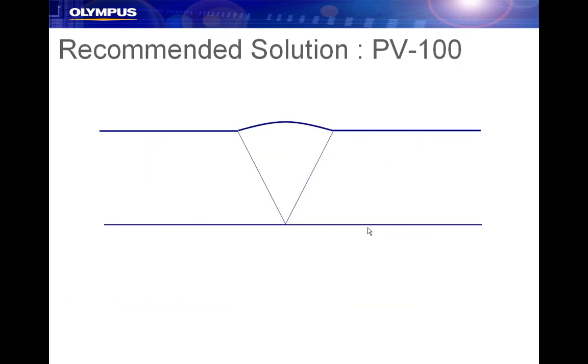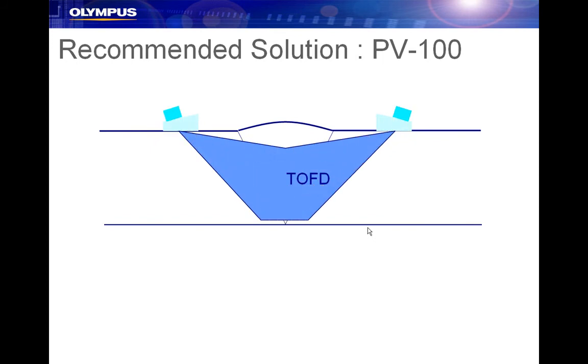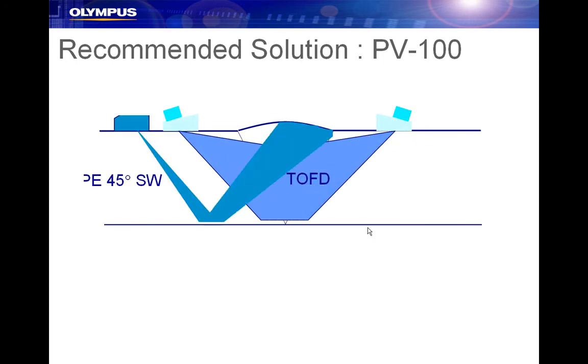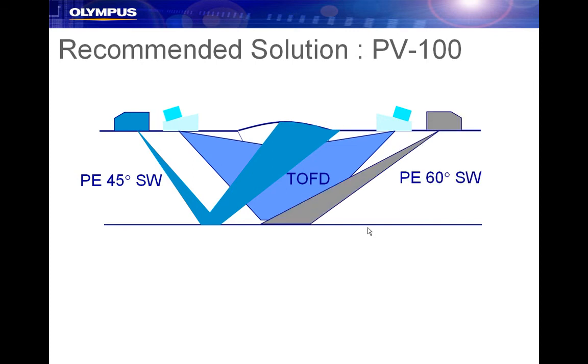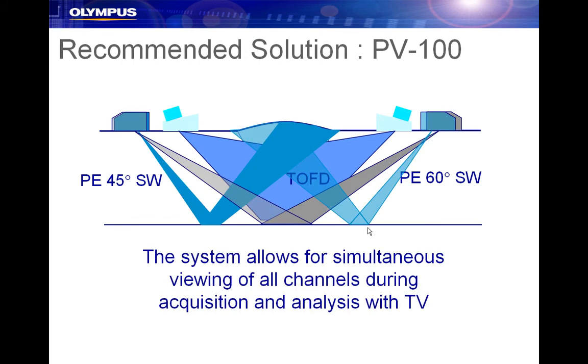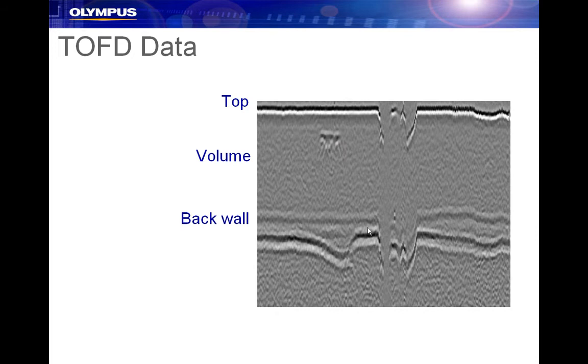The PV100 solution follows this technique, allowing for simultaneous cap, root, and volume inspection, giving full coverage with a single data set. All probe positions and angles are input, linking the individual channels into a single acquisition file in one scan or circumferential pass on the weld. When either acquired or post-analyzed in TomoView software, all channels are visible at one time. Side views are typically utilized for both the TOFD and shear wave channels.